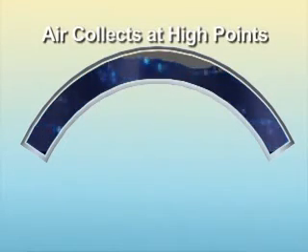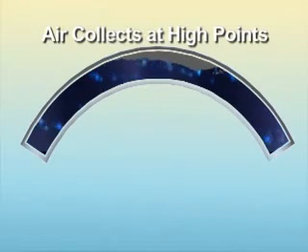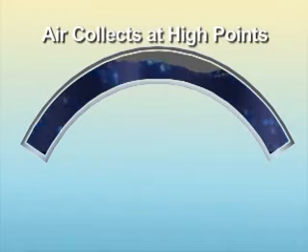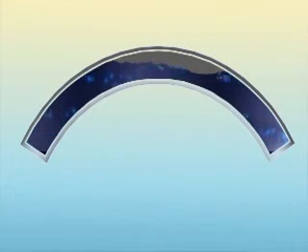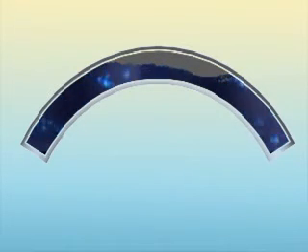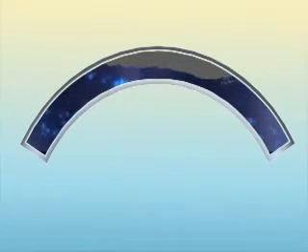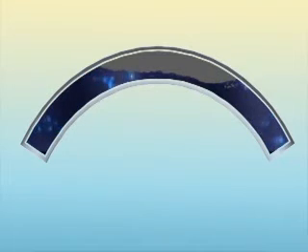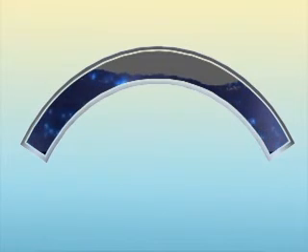As air continues to accumulate at the system high points, the fluid's velocity increases as it is forced through a smaller and smaller opening. As the pocket of air grows, one of two things will occur. The first possibility is a total flow stoppage. If system dynamics are such that the air cannot be continuously removed by the increased fluid velocity and pushed downstream, the system can become airbound, leading to complete flow stoppage. As the pocket continues to accumulate air, a pressure drop higher than pump capacity can develop and stop all flow.